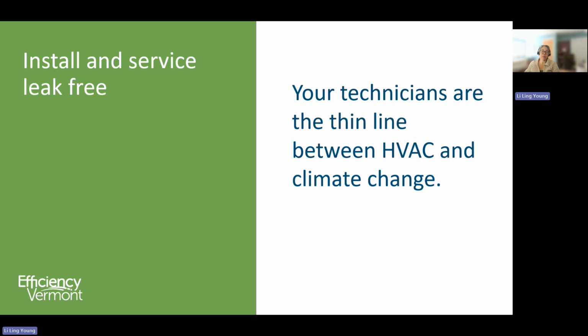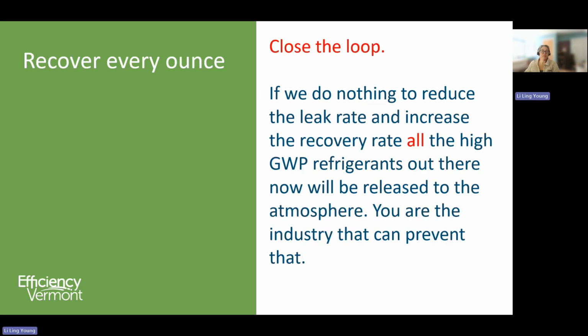Set high quality standards in your business. Train your staff and make sure every one of them is using the best tools. And then finally, at the end of life, recover every ounce of refrigerant. If we do nothing to reduce the leak rate and increase the recovery rate, all of the high GWP refrigerants out there now will be released to the atmosphere. You can recall in my previous slide that tall blue bar representing all of those highly potent greenhouse gases. Only leak repair and refrigerant recovery is going to prevent that from contributing to climate change. You're the industry that can do that.